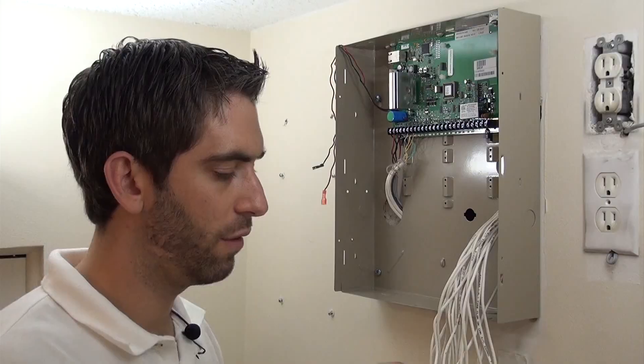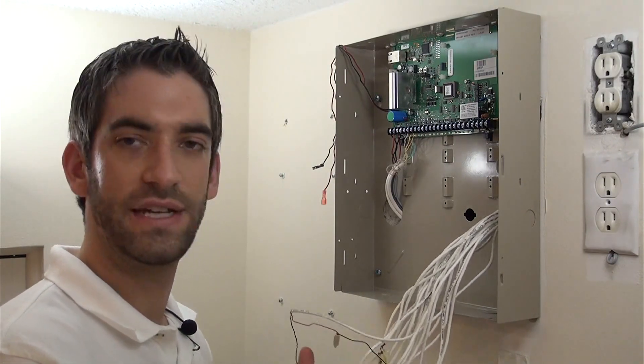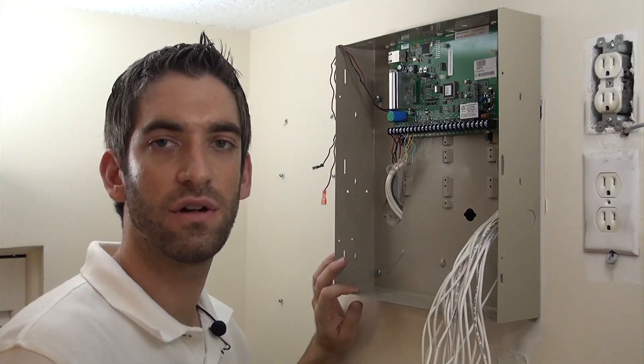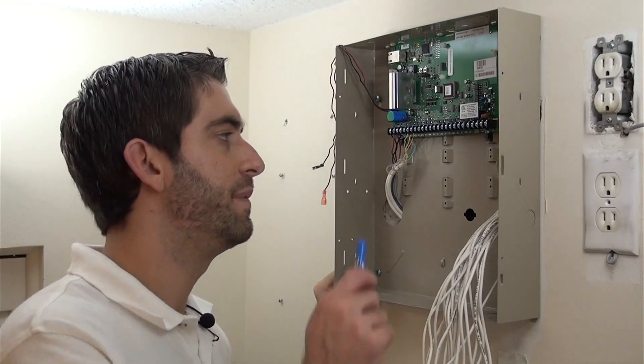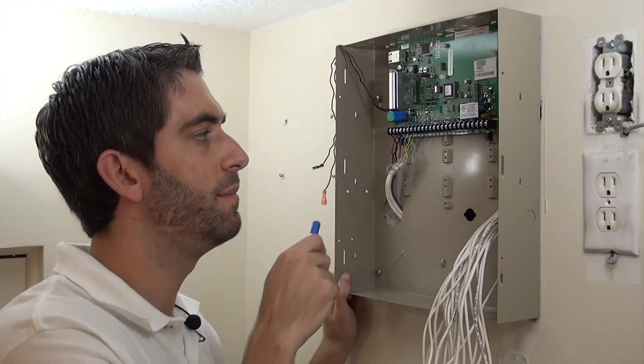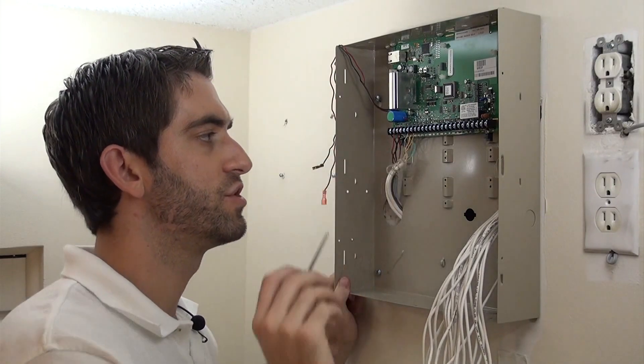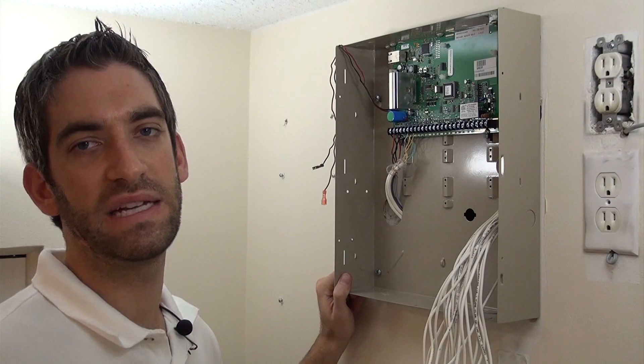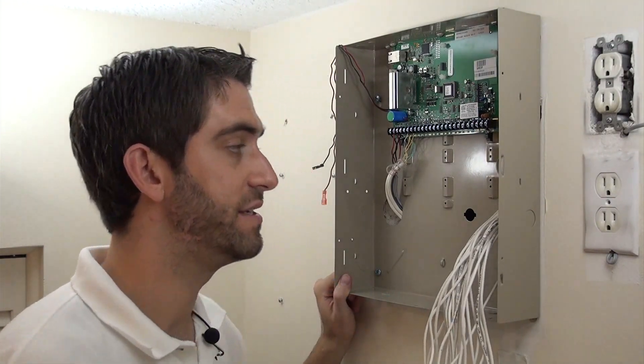And like I said from before, because we've got 14 zones here and our panel is only eight zones, we're going to use what's called zone doubling. You can't zone double zone one because that's the fire zone, but we can zone double zones two through eight to get a total of 15 zones from our base panel. And that's what we're going to do to break out these zones.